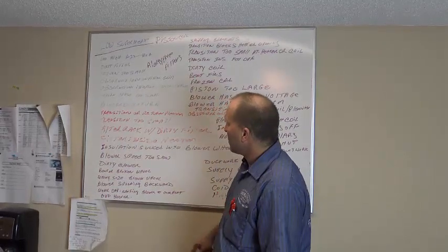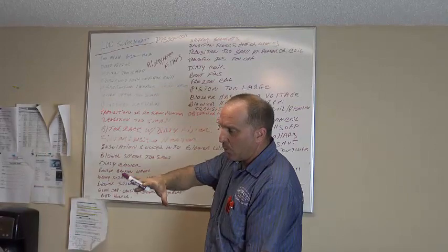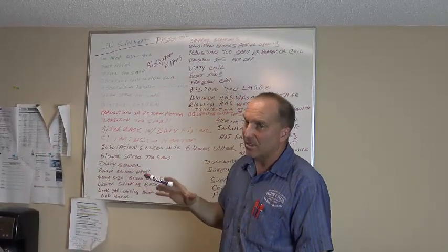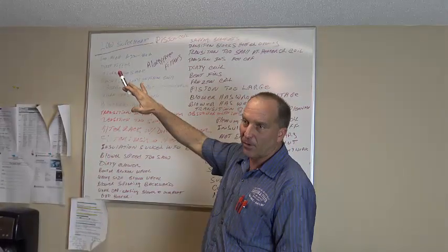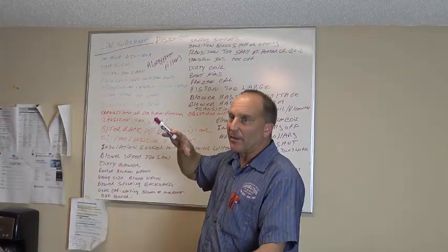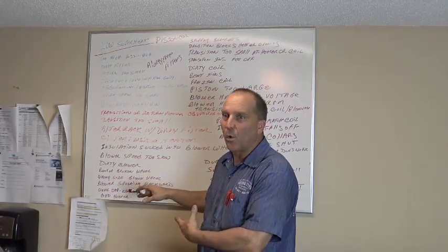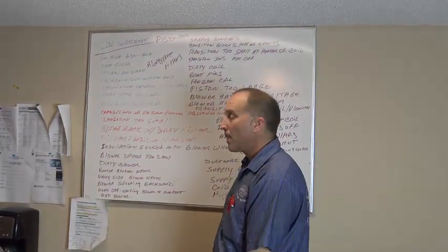Your transition is too small up in the attic, so we talked about that. If that transition comes down to a point, you have to look at the transitions, because a lot of times they take an existing hole that was there from another furnace, another return plenum, and they put a new heater in, and they'll transition to the existing hole instead of making that hole bigger to fit the new furnace.